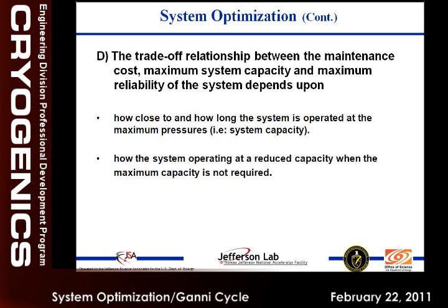Then as we developed and went into optimized processes, we did not have to run that. We started lowering below 18 atmospheres, the failures dropped and availability improved, and it made a big difference between 18 atmospheres and 20 atmospheres, because as you keep moving the pressure up another 30 pounds, it's a lot of overload on those already loaded components.